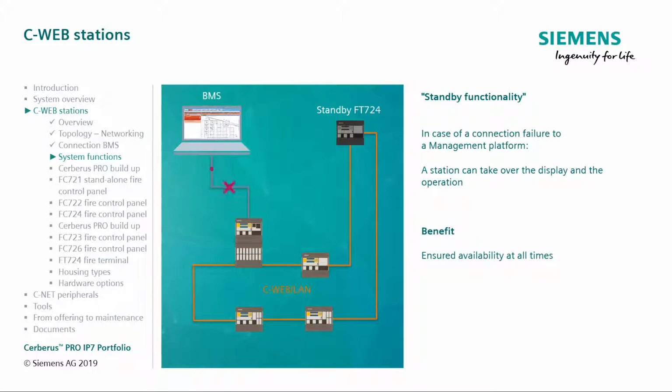But what happens if the management platform loses its connection with the network? Can the security operator still operate the system? If this happens, the standby function is automatically activated in a matter of seconds on the security operator's additional fire terminal.